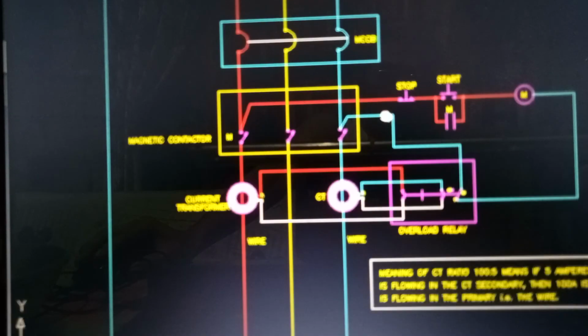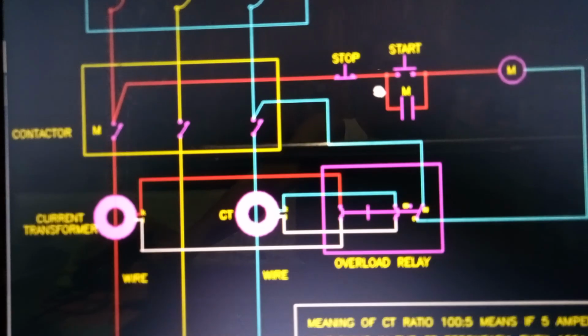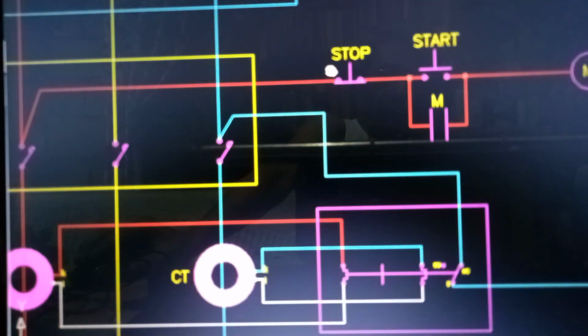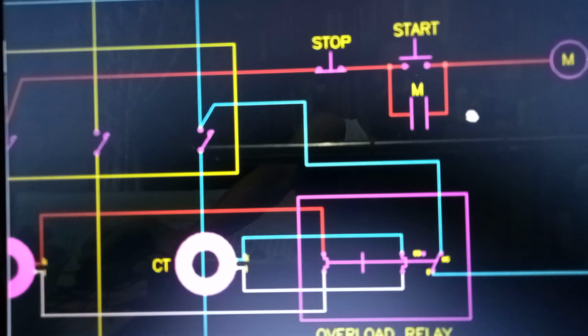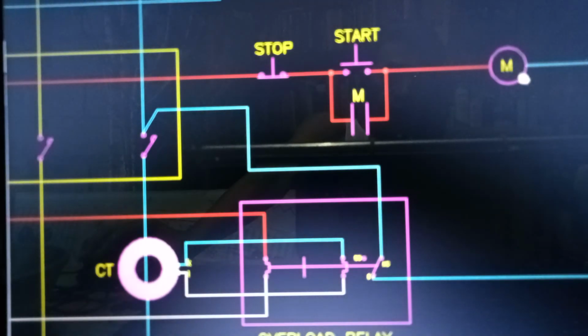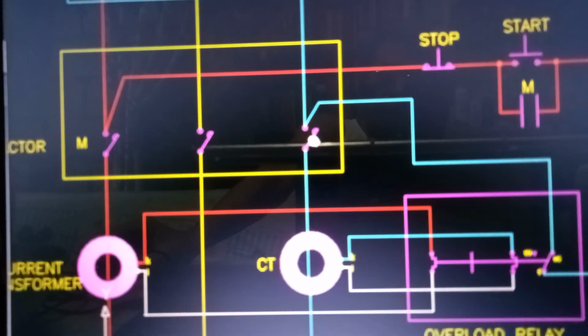So now we are going to review the schematic diagram of the full voltage magnetic starter. We have here the stop push button, start push button, holding circuit interlock, and the coil, letter M, of the magnetic contactor. So if you push the start button, the coil will be energized and the main contacts of the contactor will close, and the motor will run.